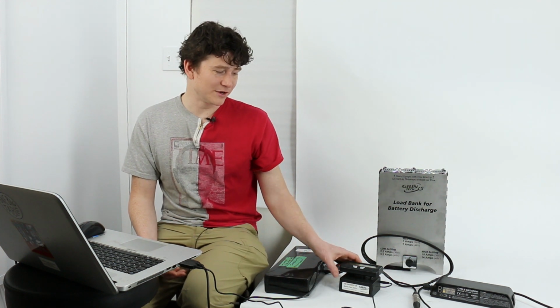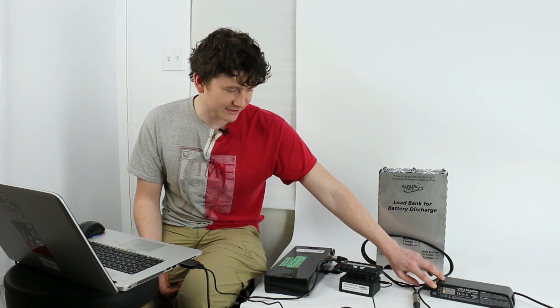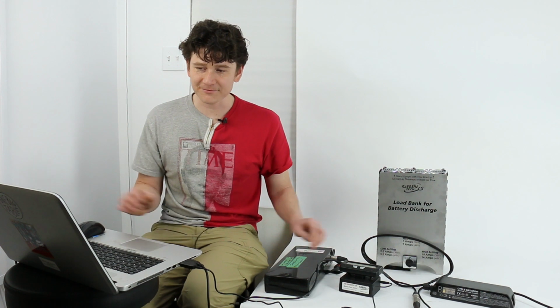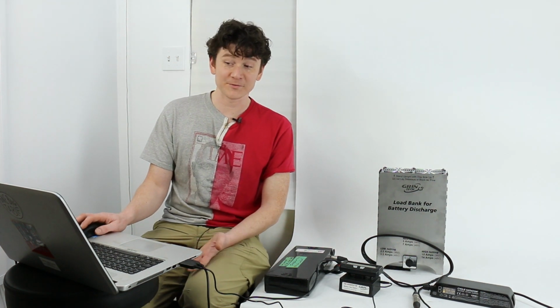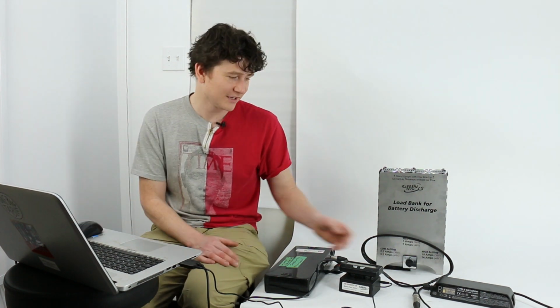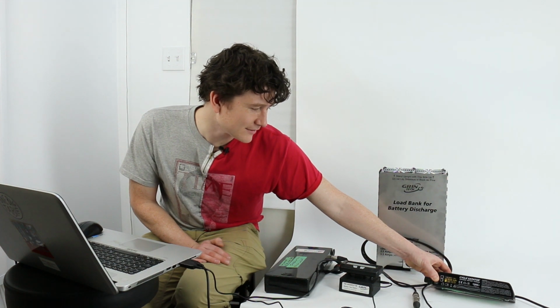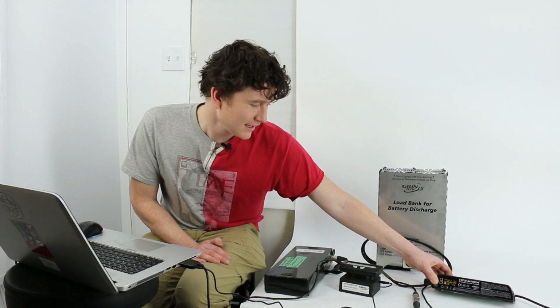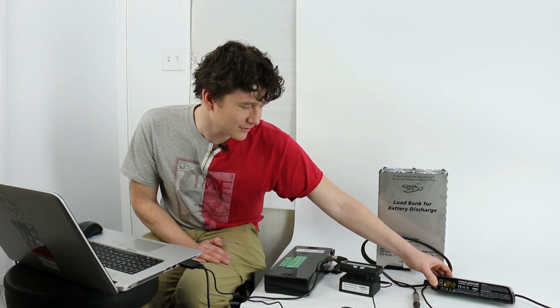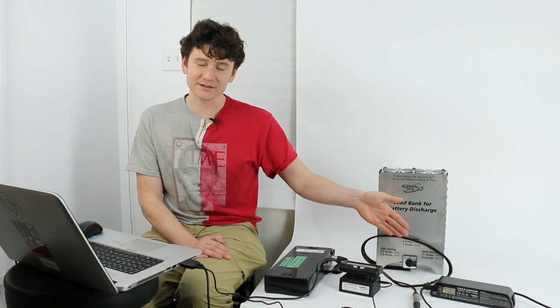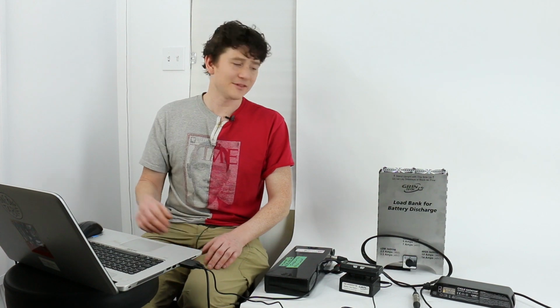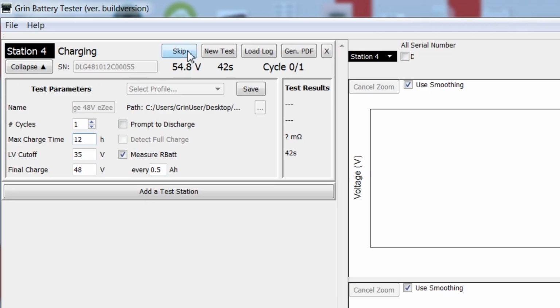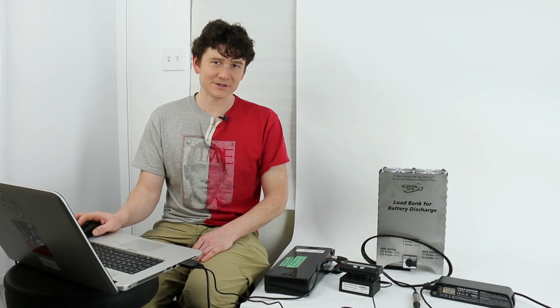In this case, the battery is already almost fully charged, sitting at 54.5 volts. 54.6 volts is the full charge voltage, and there's only about 4 amps of current flowing in. We're going to let it sit until that current trickles down to around 0.2 or 0.3 amps, and then hit skip so we don't have to wait the full 12 hours, letting the station jump to discharging.